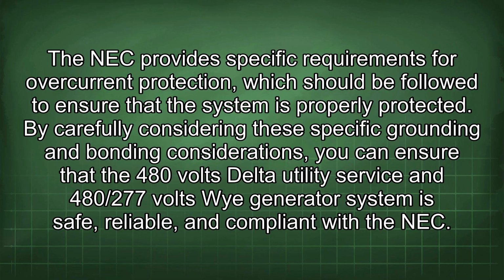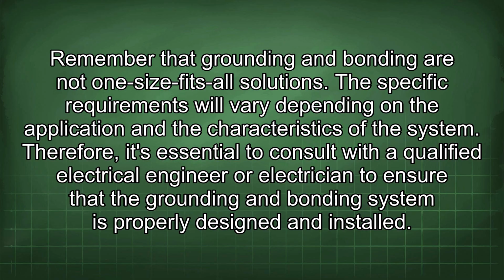By carefully considering these specific grounding and bonding considerations, you can ensure that the 480 volts delta utility service and 480/277 volts Y generator system is safe, reliable, and compliant with the NEC. Remember that grounding and bonding are not one-size-fits-all solutions. The specific requirements will vary depending on the application and the characteristics of the system. Therefore, it's essential to consult with a qualified electrical engineer or electrician to ensure that the grounding and bonding system is properly designed and installed.